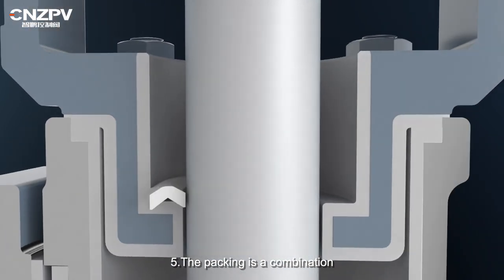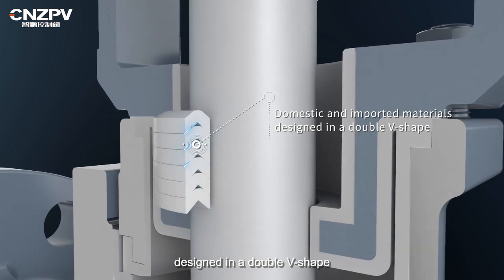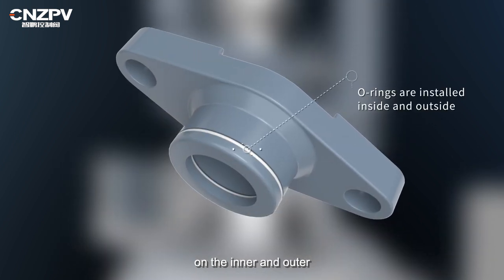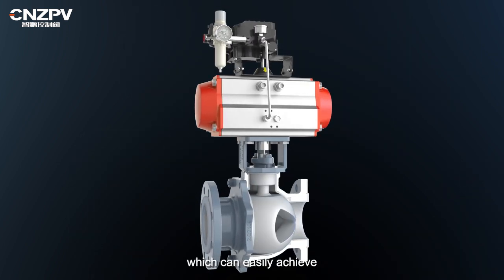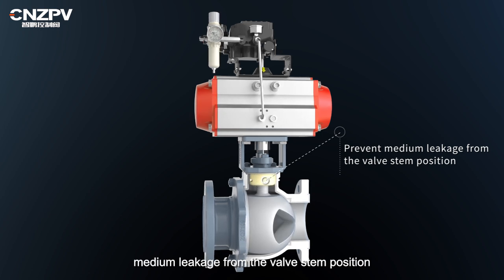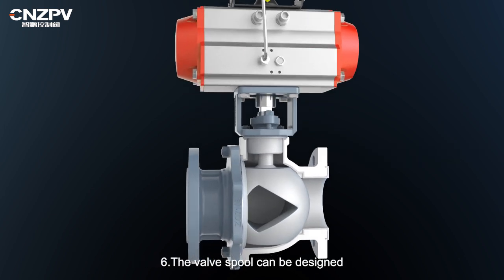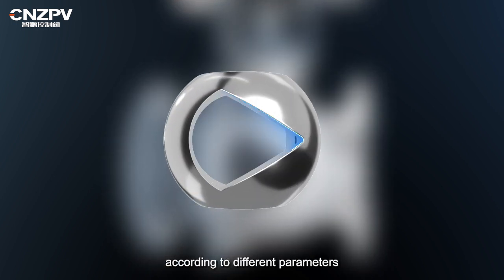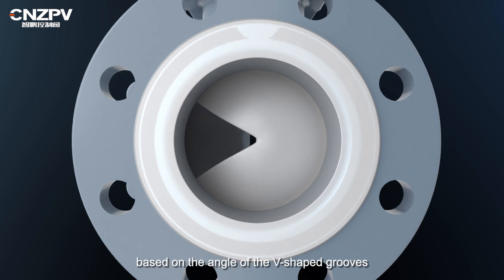5. The packing is a combination of domestic and imported materials designed in a double V-shape, which has the advantage of a large sealing area and light torque force. The O-rings are installed on the inner and outer sides of the packing gland to increase the clamping force, which can easily achieve a good sealing effect and effectively prevent medium leakage from the valve stem position. 6. The valve spool can be designed with special V-shaped grooves according to different parameter requests, allowing for precise adjustment based on the angle of the V-shaped grooves.